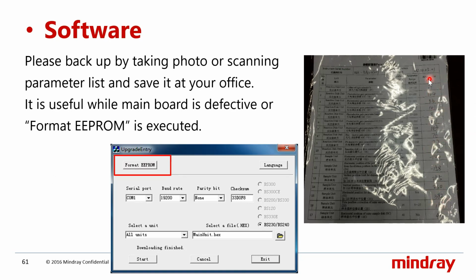That's why in the factory they define all these parameters. These are the steps you need to verify at the time of installation, or whenever you are replacing the main control PCB. Make sure the parameter file values are entered. If you have a backup, you can restore it. If you do not have a backup, you have to enter these values manually in the software. Understood? Always along with the instrument, this sheet will come. Keep it safe. It is useful when the mainboard is defective or format EEPROM is executed.